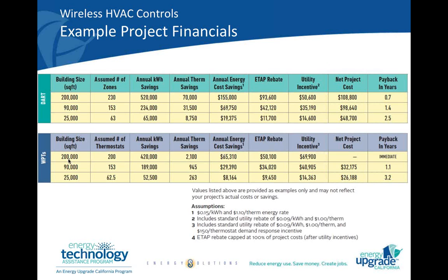So finally, here are just some example projects for both DART and WPTs. And the things to zero in on, the annual kWh savings and therm savings are calculated as I previously described based on facility data. The cost of the project is going to depend on the characteristics of the system. For DART, it'll depend in part on the number of zones controlled and on the number of fans being controlled. For WPTs, it's going to depend on the number of thermostats.